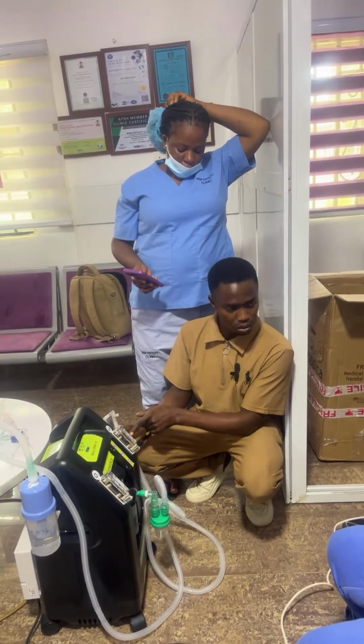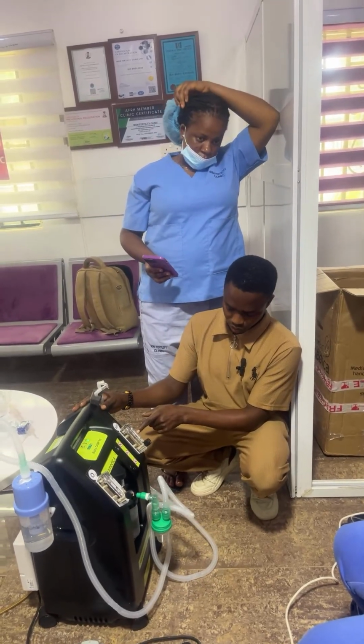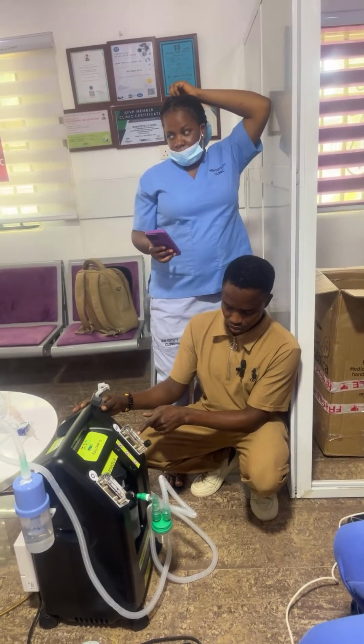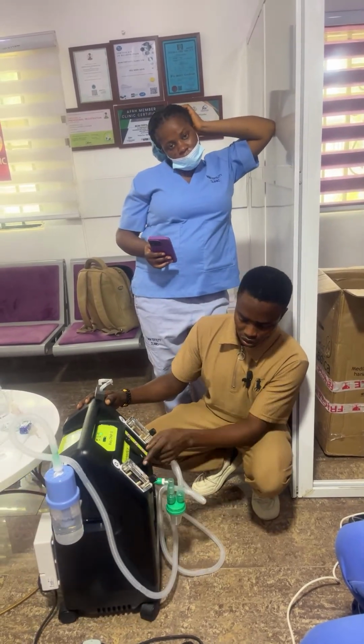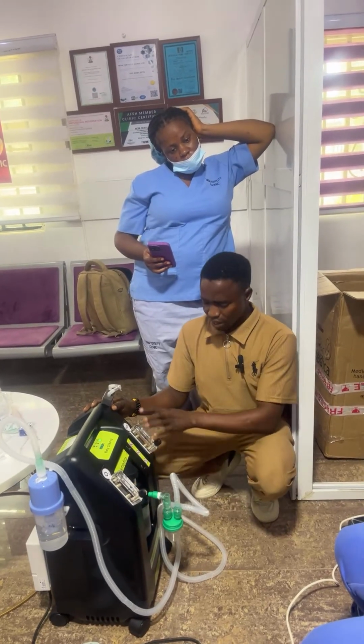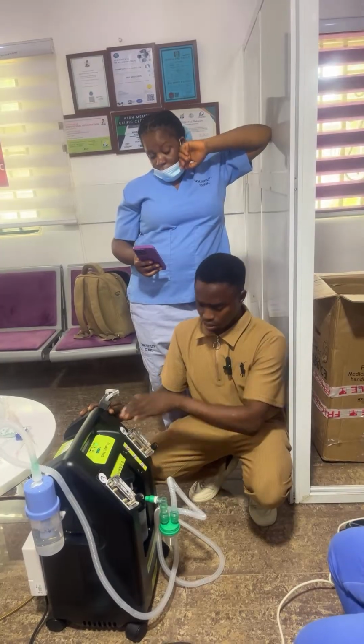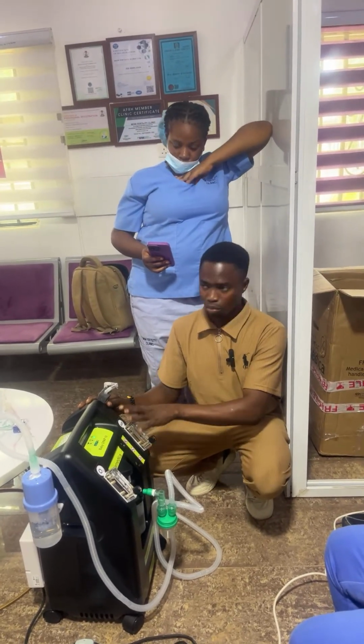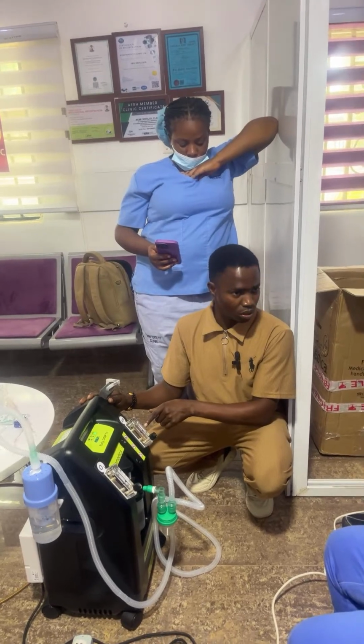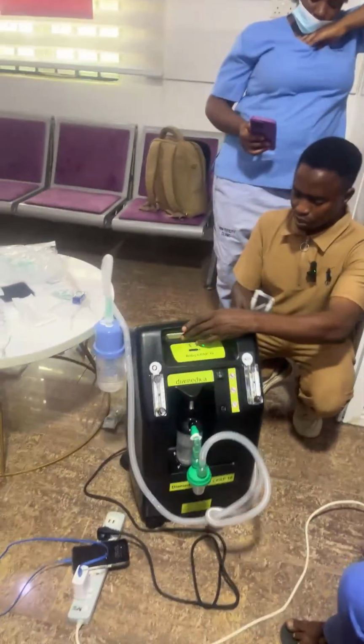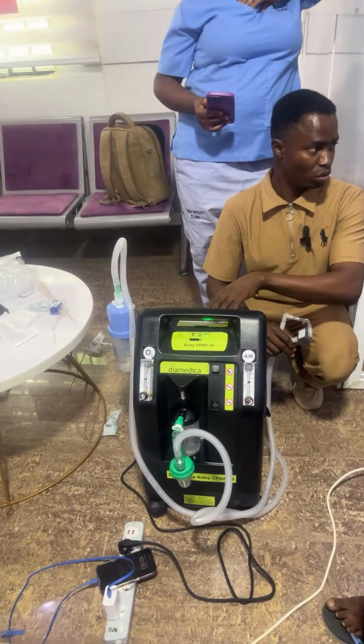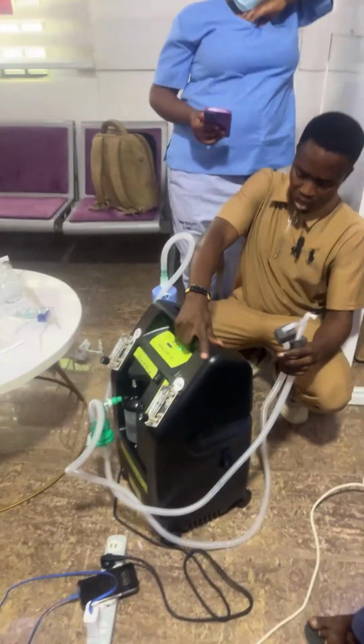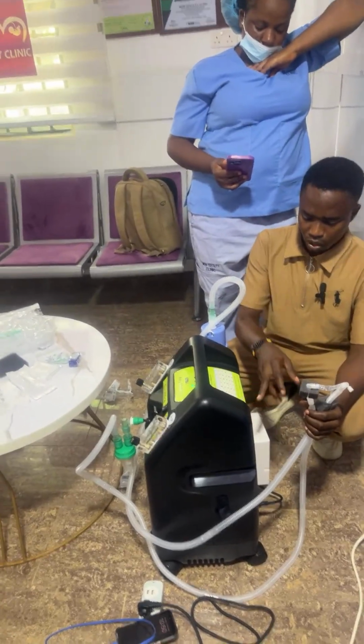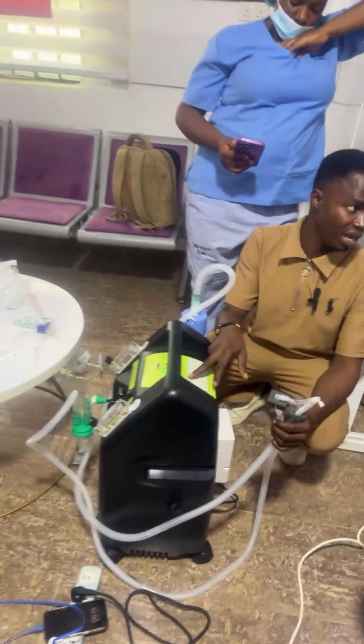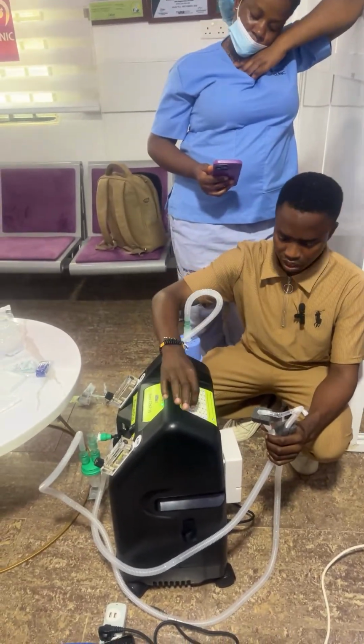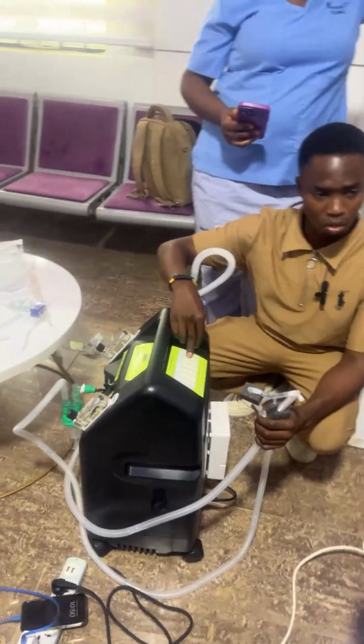Of air. This tells you that the air is on 3, then the oxygen is on 2. Meanwhile, this can look more stable than this based on the way it's working inside, but that's not a big concern. You can see it's not very stable because it's here. Then 2 is on how to set the chart, the FiO2. So we have the vertical and the horizontal column. The vertical column now is our airflow meter. The oxygen is this horizontal.